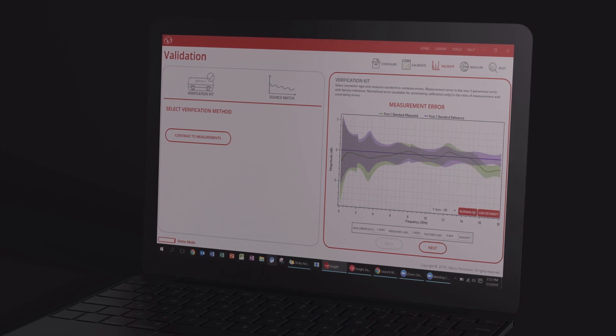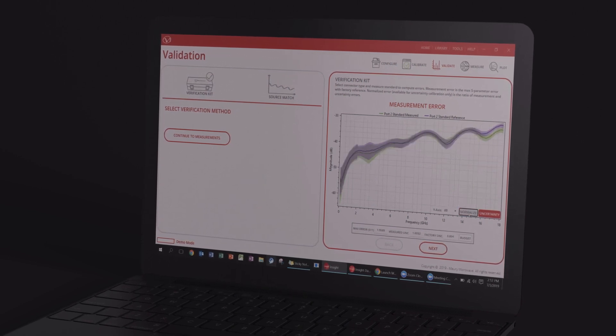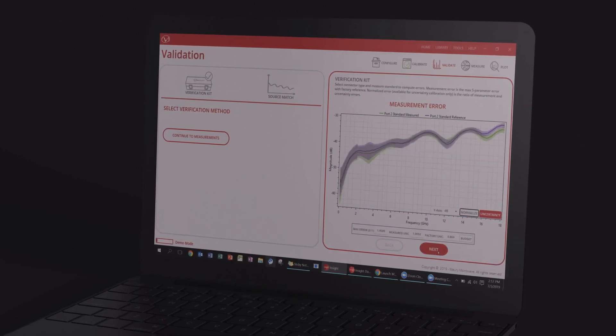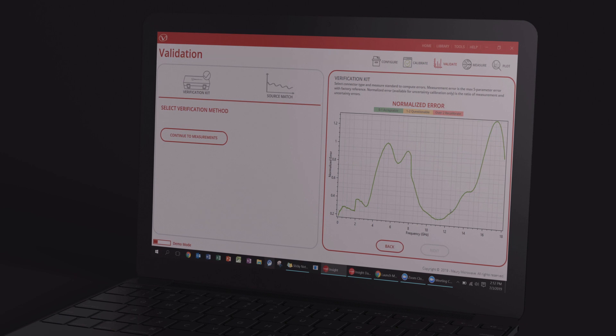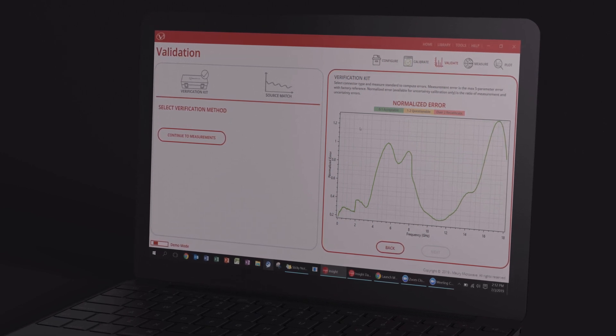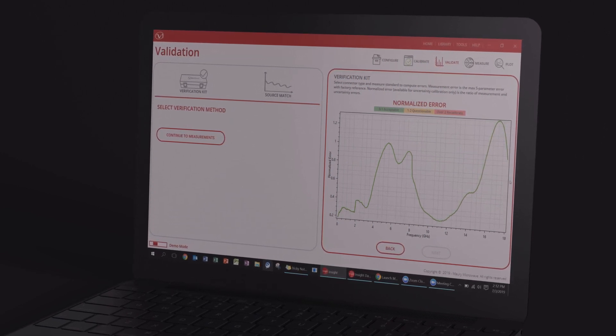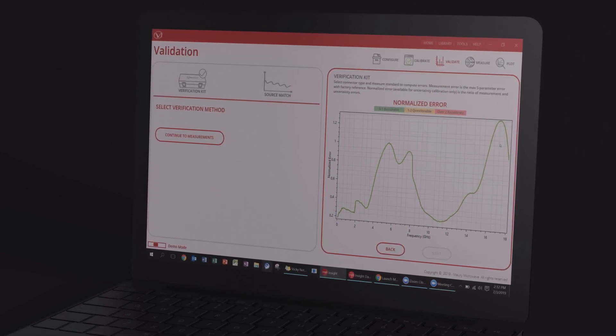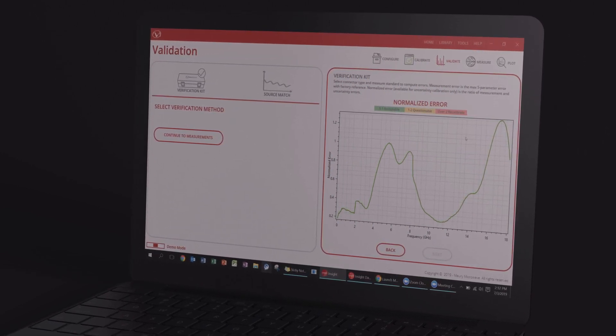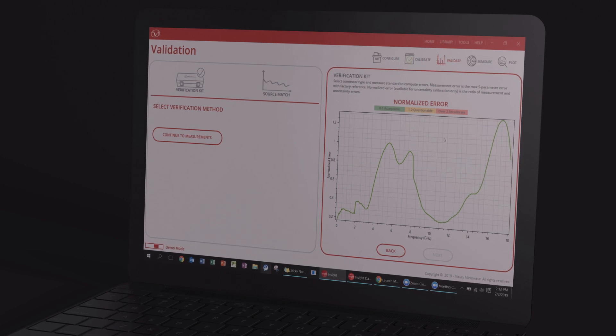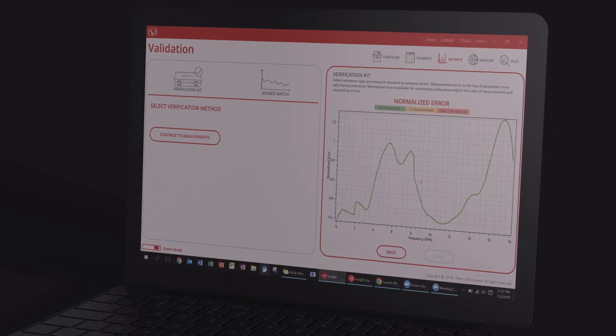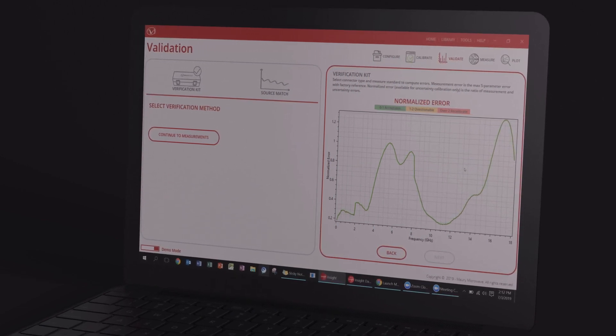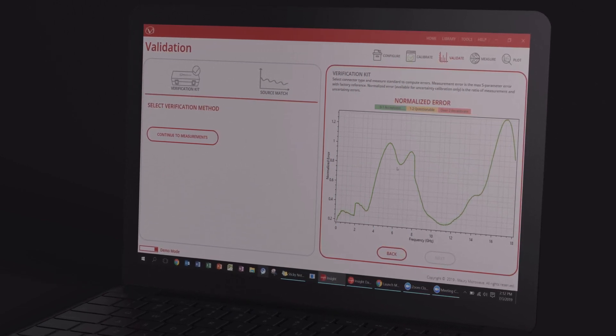The S-parameters measured by Maury Microwave are supplied with the verification kit. The S-parameters and uncertainty boundaries are both displayed, and an overlapping uncertainty area reassures users of a successful and accurate calibration.